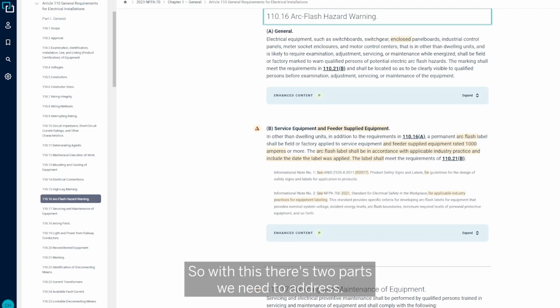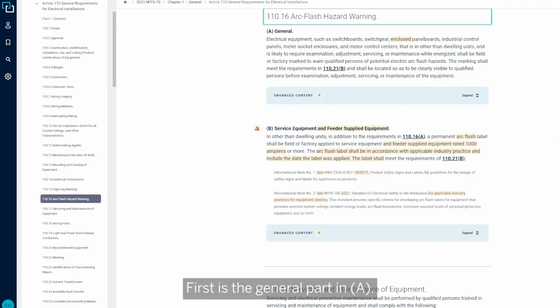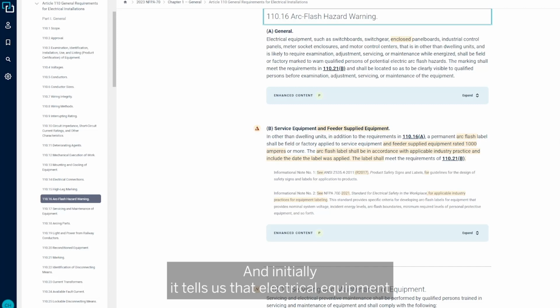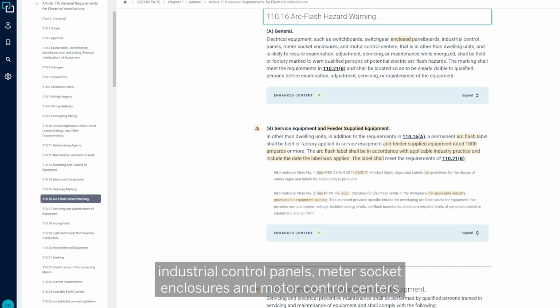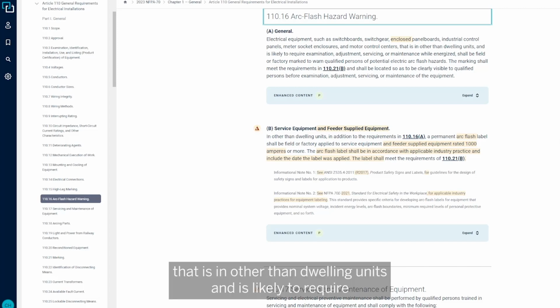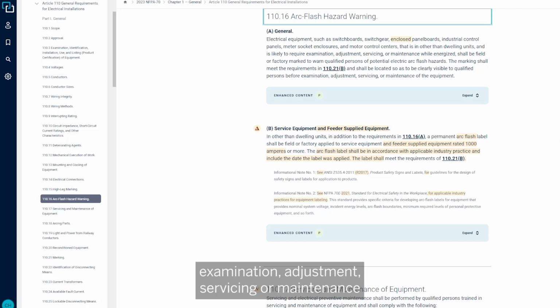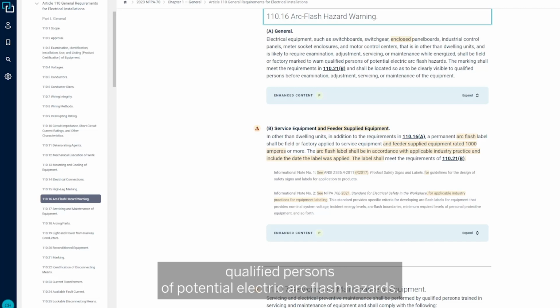So with this, there's two parts we need to address. First is the general part in A. And initially it tells us that electrical equipment such as switchboards, switchgear, enclosed panelboards, industrial control panels, meter socket enclosures, and motor control centers that is in other than dwelling units and is likely to require examination, adjustment, servicing, or maintenance while energized shall be field or factory marked to warn qualified persons of potential electric arc flash hazards.